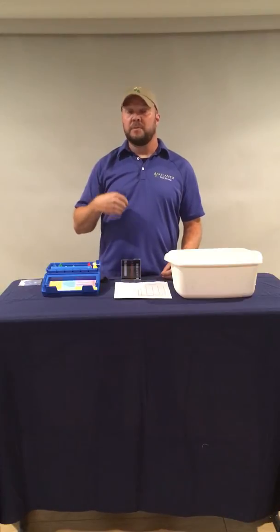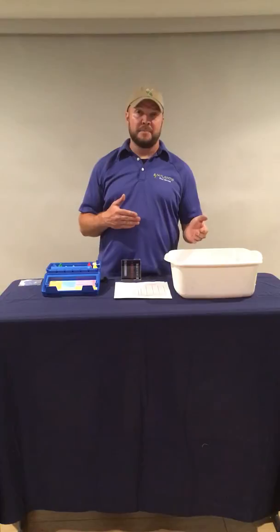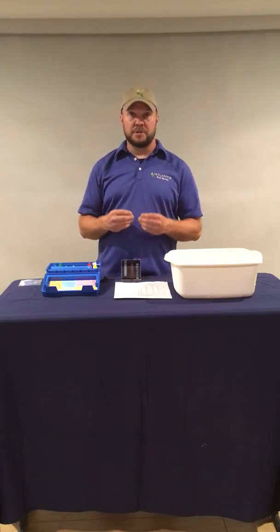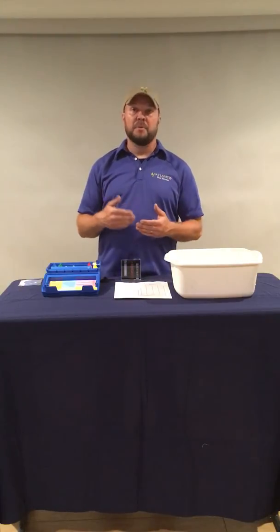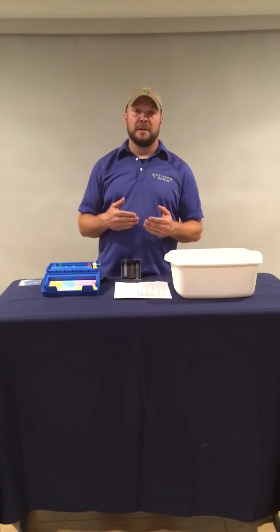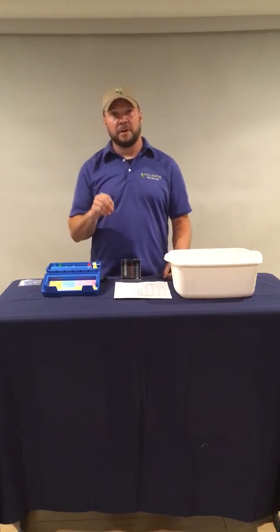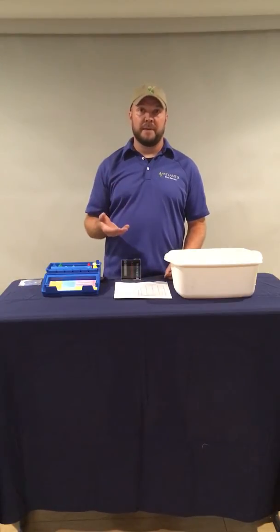The total alkalinity, when you have it balanced properly, and the target range that we're generally going for is 80 parts per million to 120 parts per million. If you have your total alkalinity where it should be, the pH is buffered. It's not going to be prone to those wild fluctuations as it would be if you had no total alkalinity. So it's really important to get your total alkalinity where it should be, and then you'll have far less problems with pH on a daily basis.